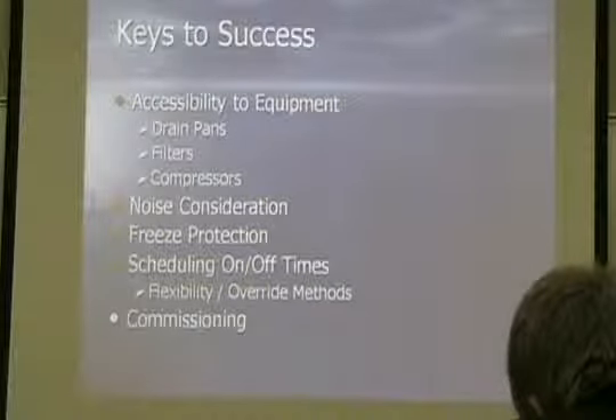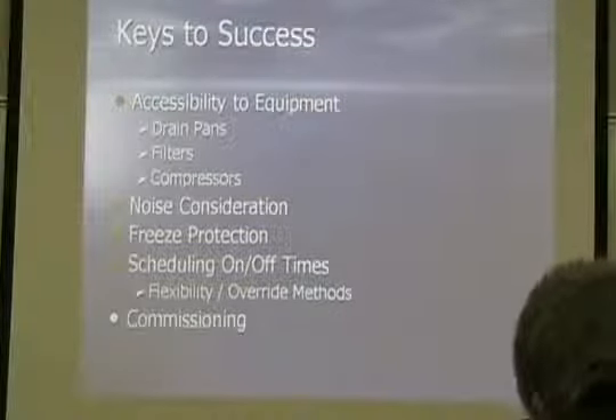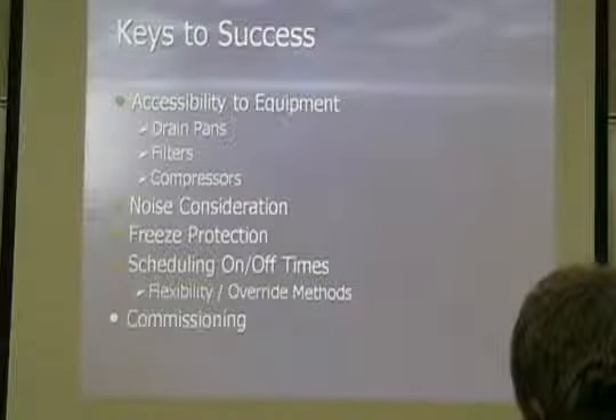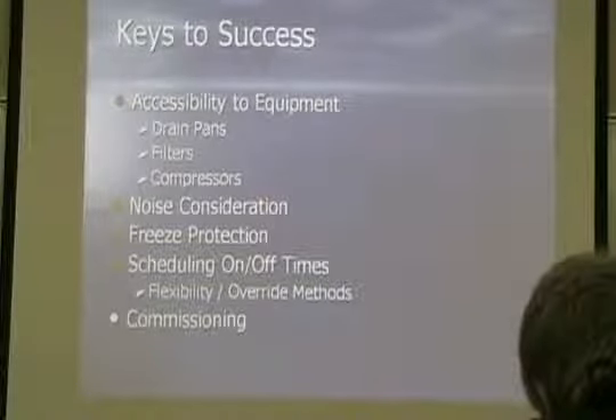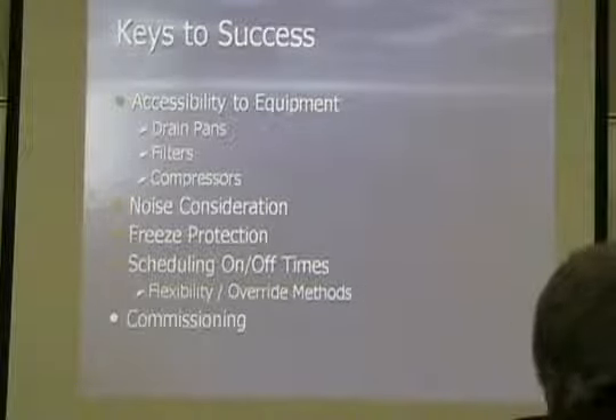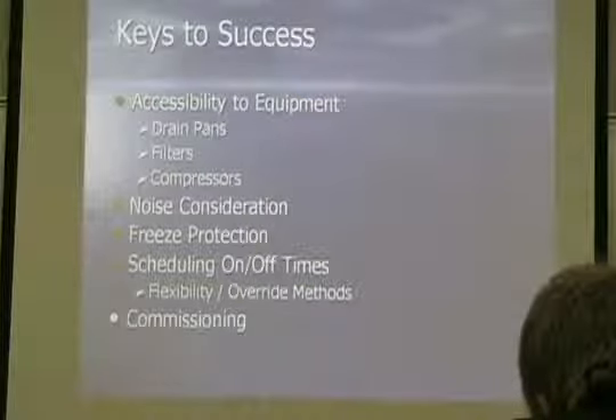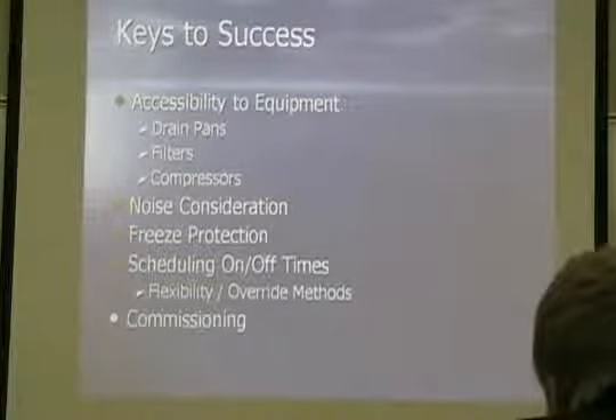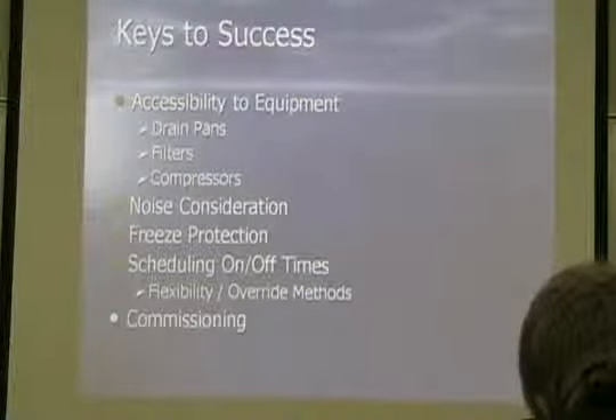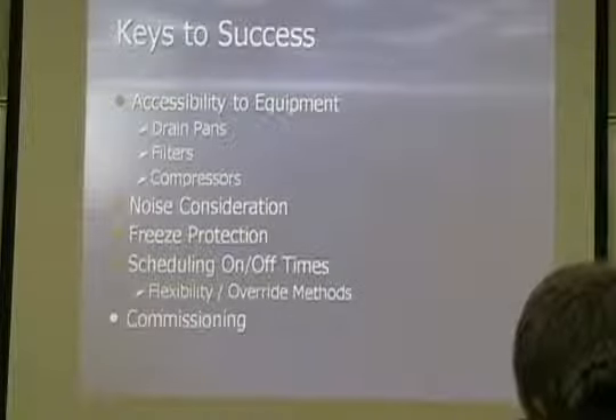Scheduling on-off times, like I said, you could add controls to these things and do anything you want as far as scheduling them on and off, night periods, unoccupied periods. They're pretty easy to commission. Like I said, it's just a simple piece of equipment. It's a compressor and a fan, with a 5-wire thermostat, or you can put a controller similar to a VAV box controller on it to tie it into a front-end control system.